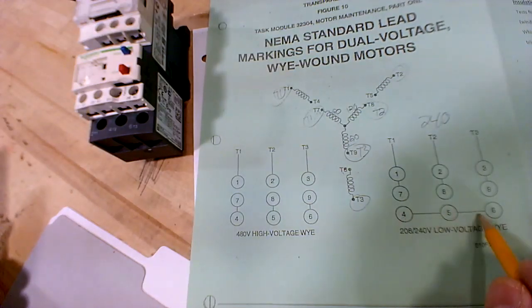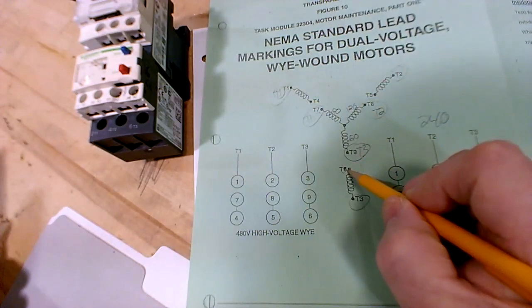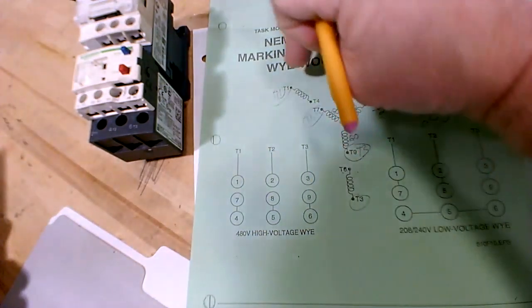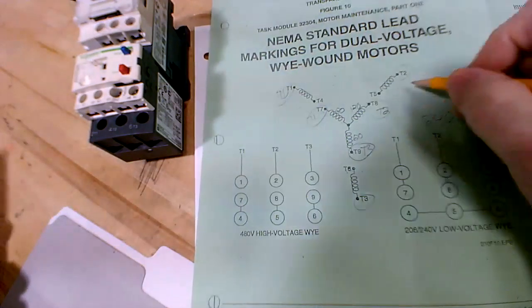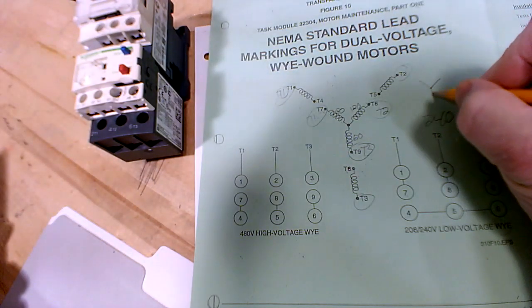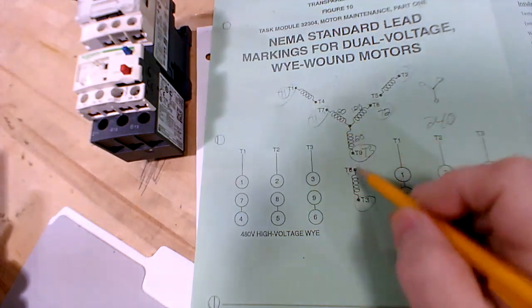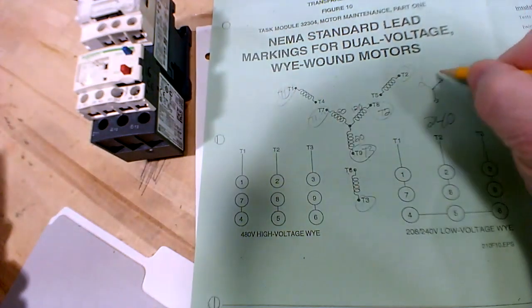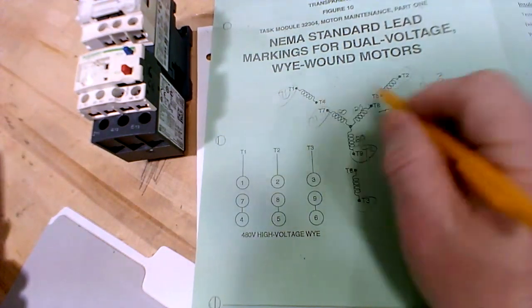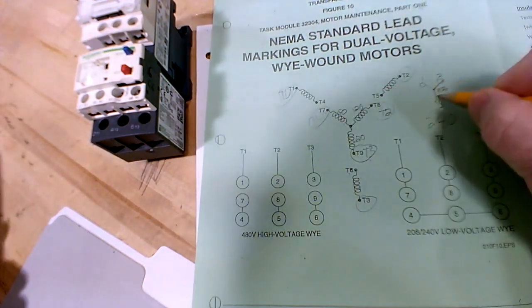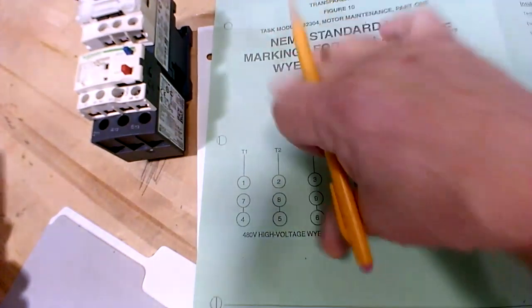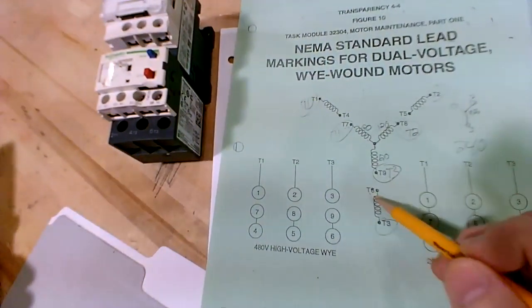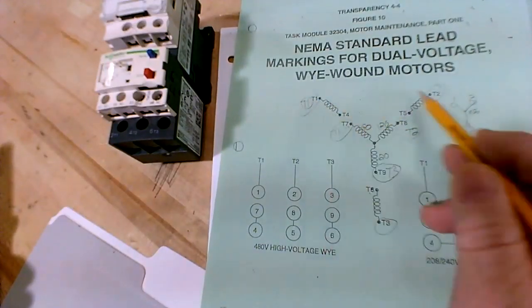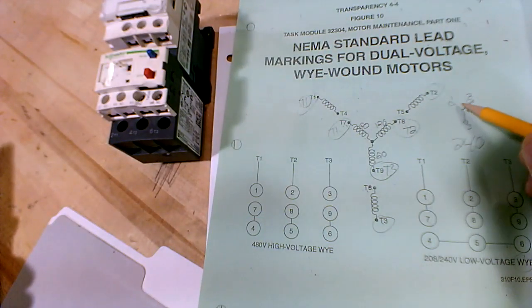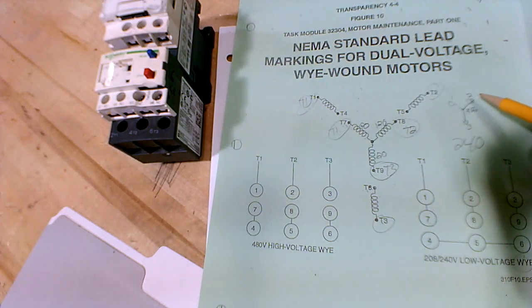Now, when you do 4, 5, and 6 together, you put 4, 5, and 6 together, you're producing another Y with these 3. You're basically moving them out to the side, and you're doing this. You're producing another Y here with 1, 2, and 3 on the outside. 1, 2, and 3, and the center is 4, 5, 6. 4, 5, 6. You see that? So you produced out of these 3. You moved them out and done this, and in this one you have T1, T2, and T3, right? So if I measure here to here, what do I have? I've got 240.